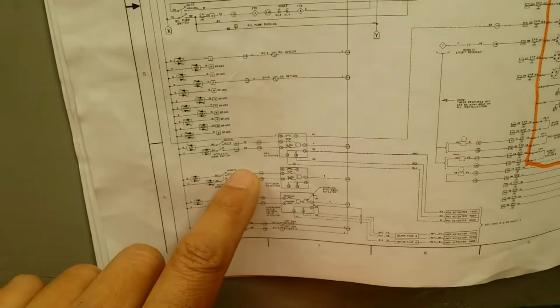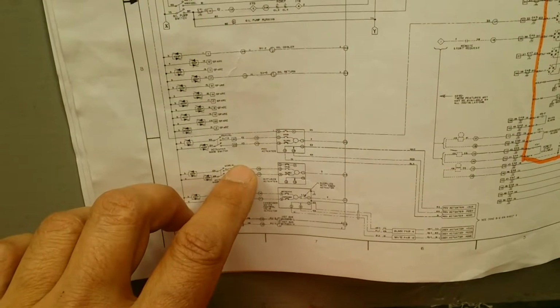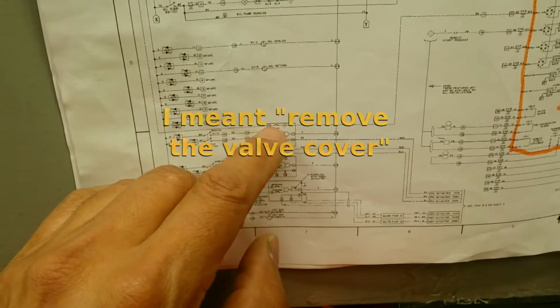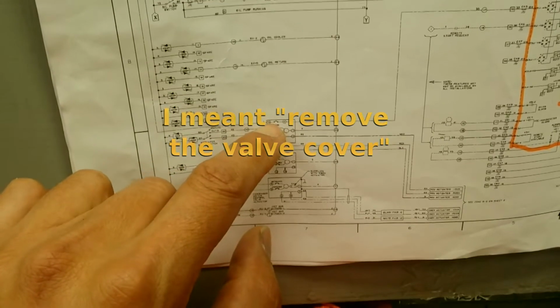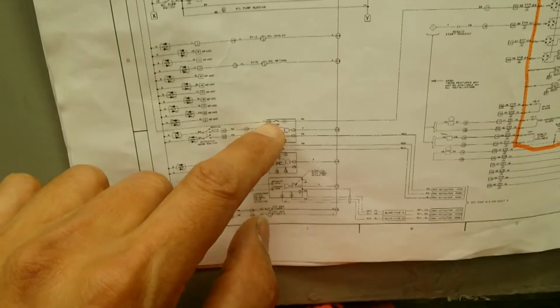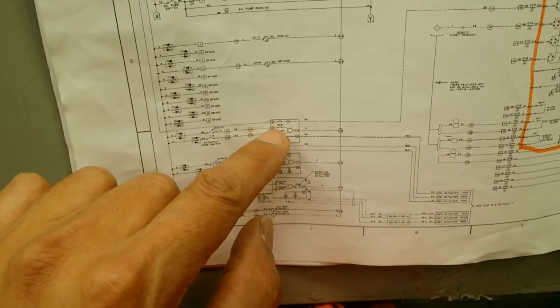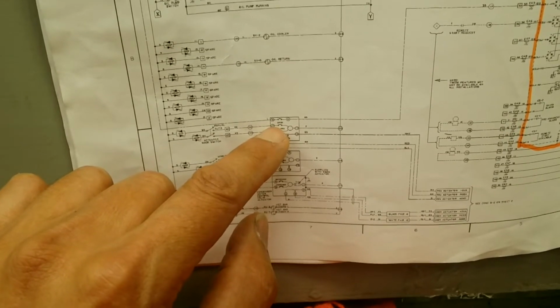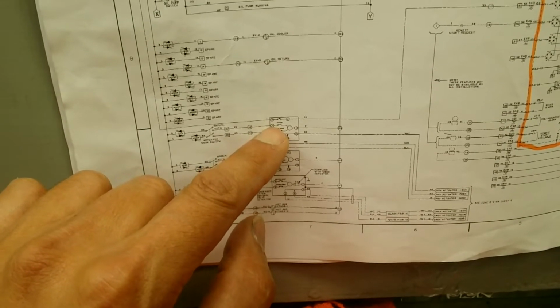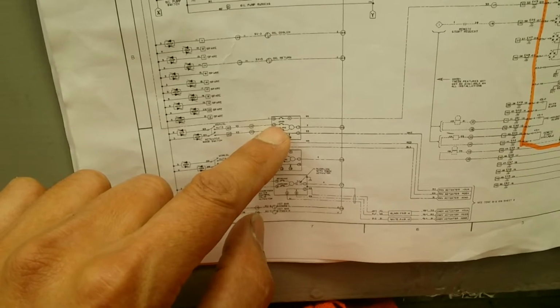But instead of removing the SSR, what I will do is get an energized sheet, go to the valve, remove the valve, and put one pin of the multimeter into one, which happens to be a common, and then another one into the command that I think is not getting power. Let's say the valve opens, and then I will command the valve to open from the microprocessor screen module.